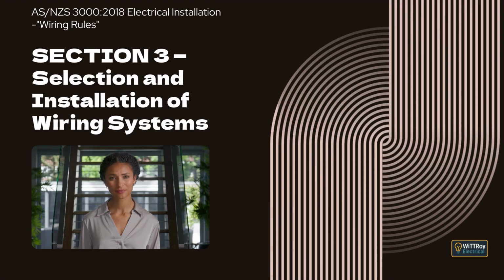Today we're moving into Section 3, Selection and Installation of Wiring Systems, which focuses on wiring systems. In this section, we'll look at how cables and wiring systems must be selected, installed, supported, protected, and enclosed so they remain safe throughout their service life. Everything in this section is about good installation practice, preventing damage, managing heat, allowing for movement, and making sure wiring systems are suitable for the environment they are installed in. This section sets out the practical rules electricians use every day on site, and it links closely with earlier safety principles to make sure installations remain reliable, durable, and safe under normal use and foreseeable conditions.